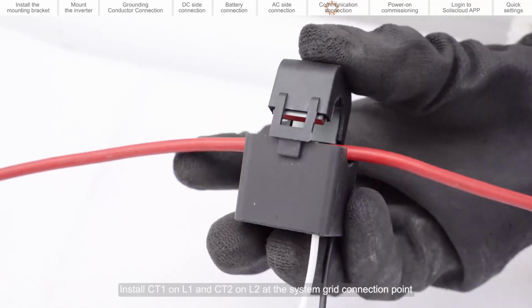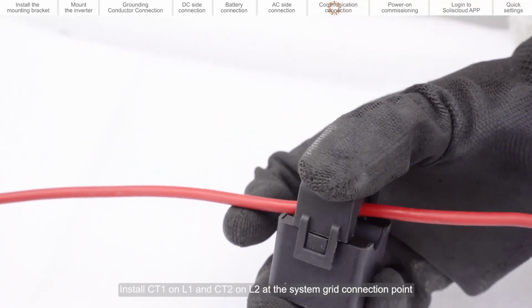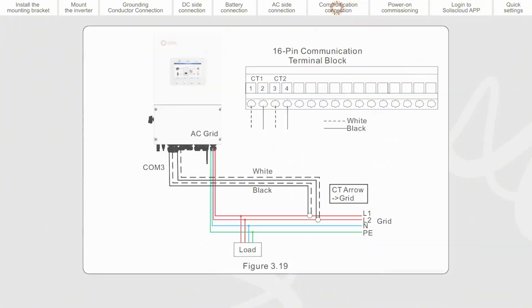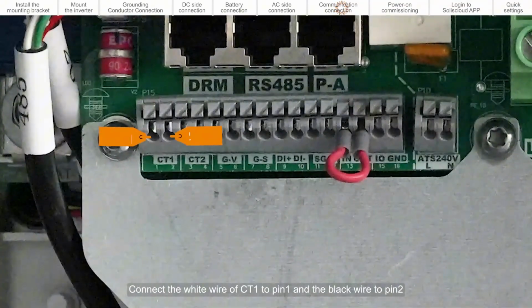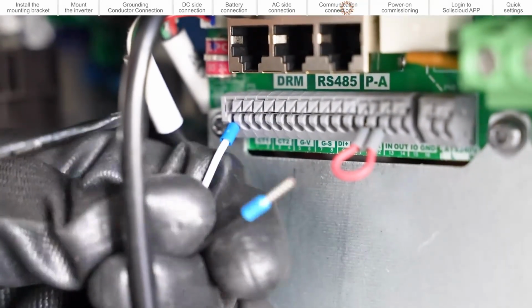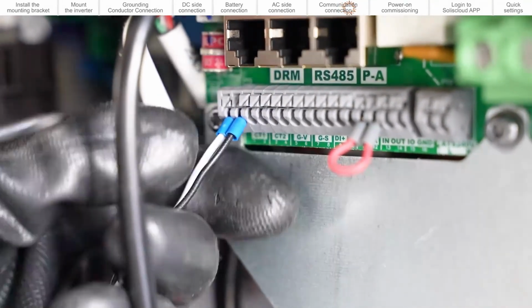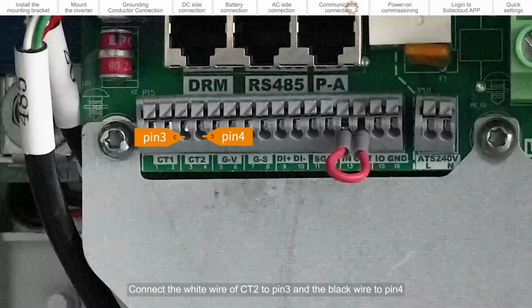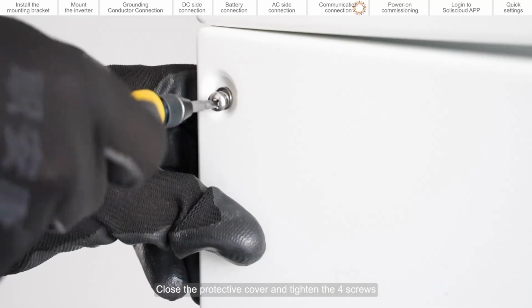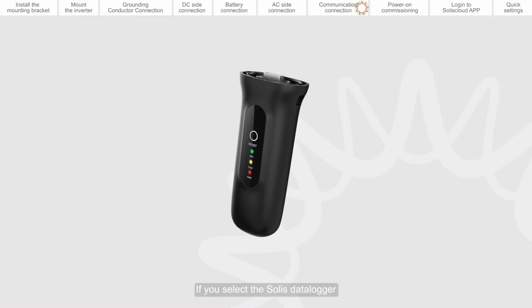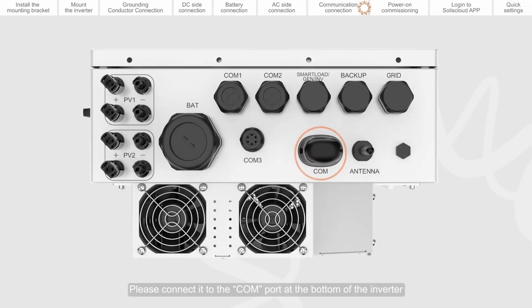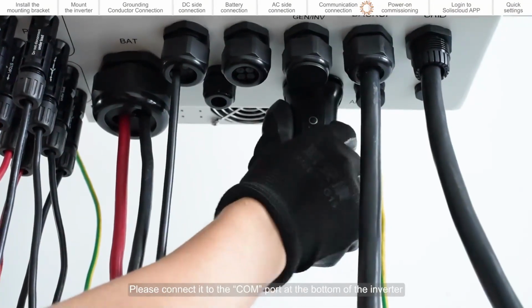Install CT1 on L1 and CT2 on L2 at the system grid connection point. The CT arrow should point to the grid. Connect the white wire of CT1 to pin 1 and the black wire to pin 2. Connect the white wire of CT2 to pin 3 and the black wire to pin 4. Close the protective cover and tighten the 4 screws. If you select the Solis data logger, please connect it to the COM port at the bottom of the inverter.